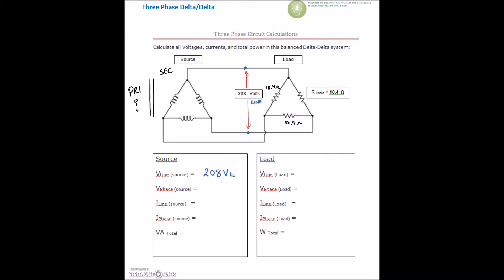But we can also see that, or remember that with these guys, they're more of a parallel circuit. And so for these delta circuits, we know that V line is equal to V phase. So that voltage right there is the same as this voltage right here, which is the same as this voltage right here. So we can see that the voltage on the phase is 208 volts on the phase as well.